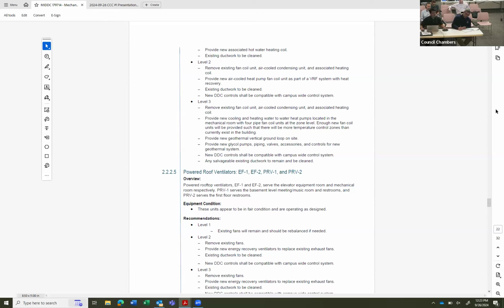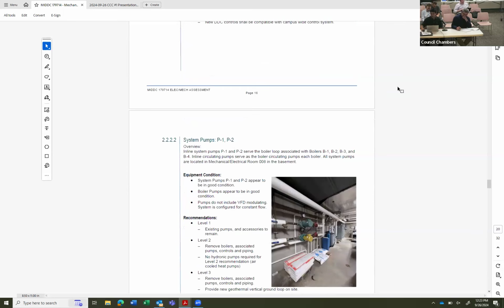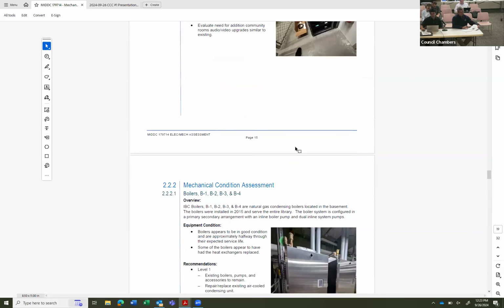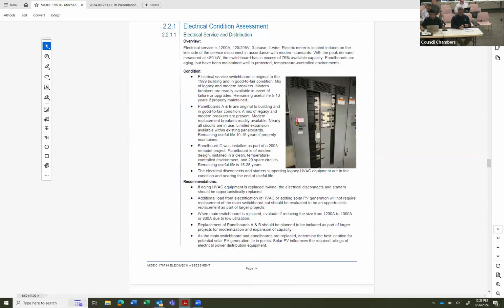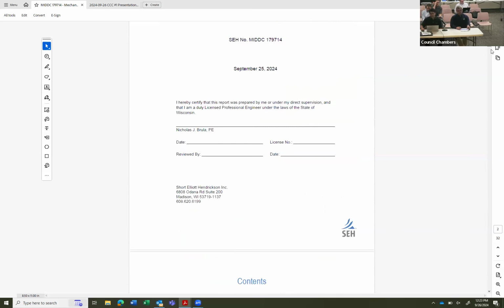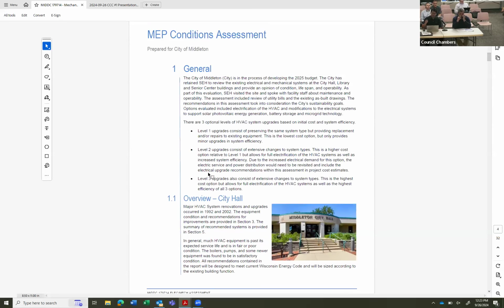Right. Chase Hendricks here. I'll be going over the HVAC and plumbing. To start out, I'll summarize the HVAC. We've provided three different levels of optional upgrades. The first level is replacing or upgrading the current equipment, replacing it in kind with a newer unit that will fit in the same spot and connect to the same duct and pipe connections. That would still use a lot of the same type of equipment and wouldn't provide full electrification of the HVAC system, but would provide some efficiency upgrades.